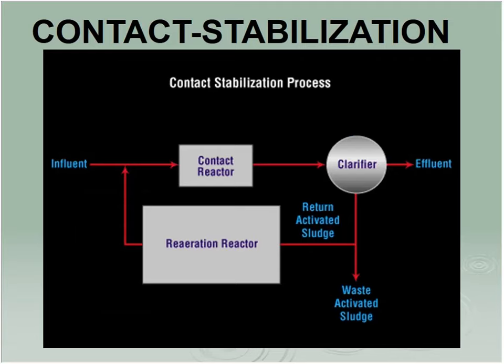And in this reactor, the bugs are going to adsorb the food to their bodies. They're not going to break it down, they're just going to pick it up. We're going to run them into the clarifier, settle them out, and then send them to a re-aeration reactor for 3 to 6 hours. That's where they actually break down the food, stabilize, and also repopulate quite a bit. We've got a much higher population in here than we do in this tank.